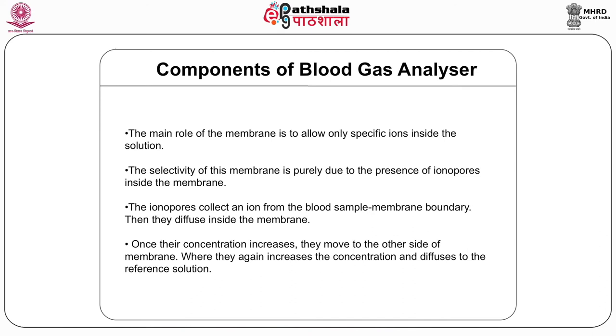The specificity of this membrane is purely due to the presence of ionophores inside the membrane. The ionophores collect an ion from the blood sample and membrane boundary. They then diffuse inside the membrane, and once their concentration increases, they move to the other side of the membrane, where they again increase the concentration and diffuse to the reference solution.